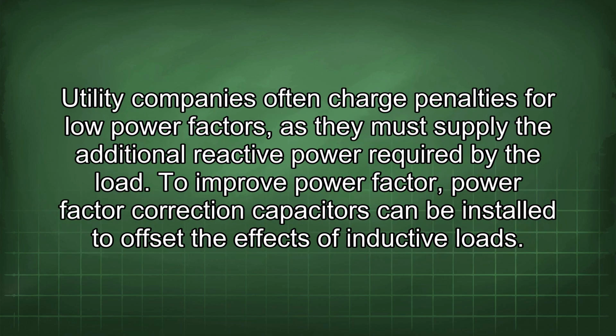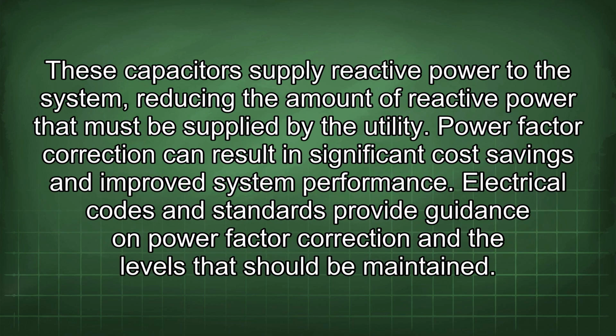Utility companies often charge penalties for low power factors, as they must supply the additional reactive power required by the load. To improve power factor, correction capacitors can be installed to offset the effects of inductive loads. These capacitors supply reactive power to the system, reducing the amount of reactive power that must be supplied by the utility. Power factor correction can result in significant cost savings and improved system performance.